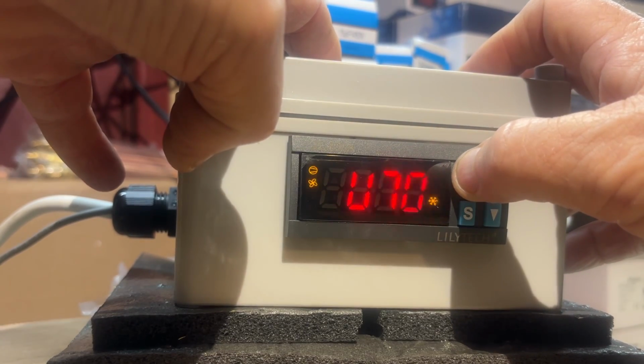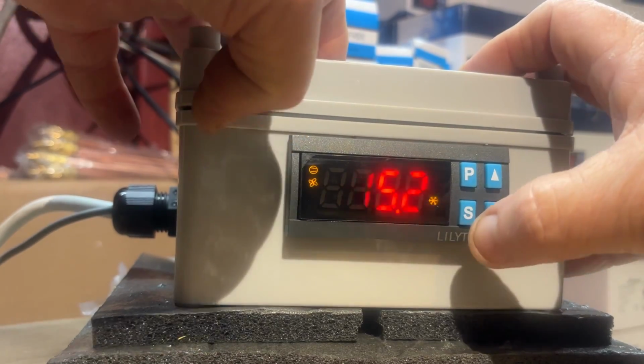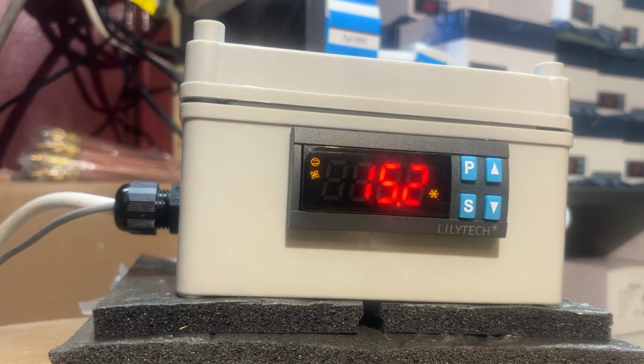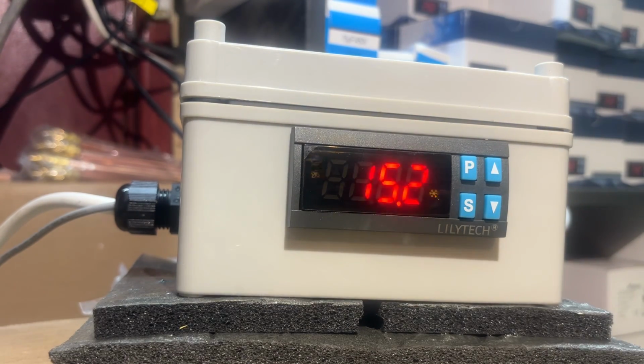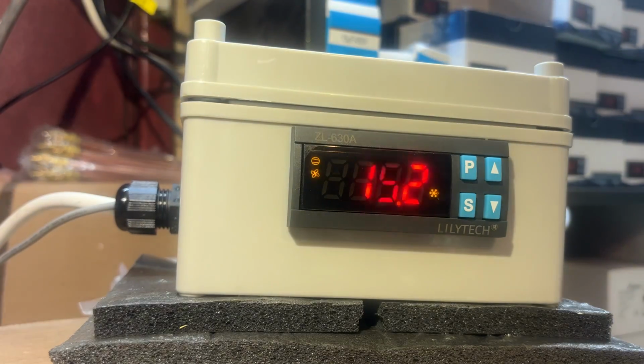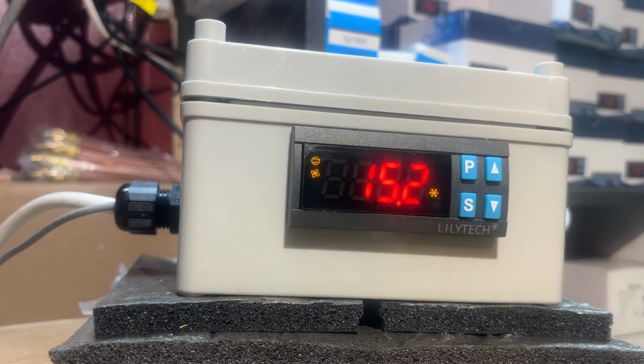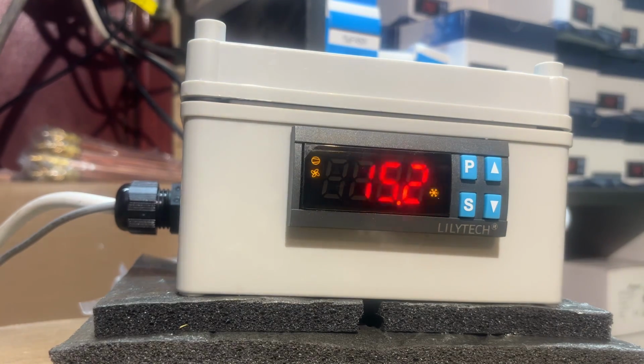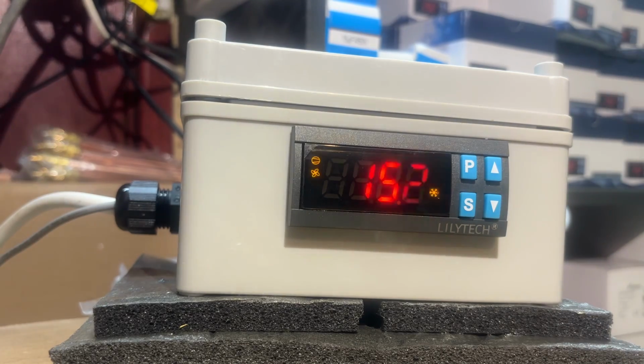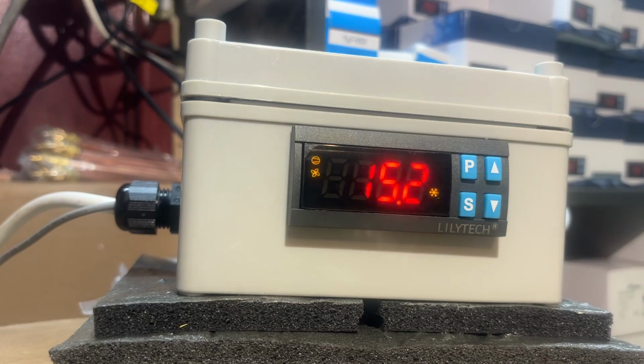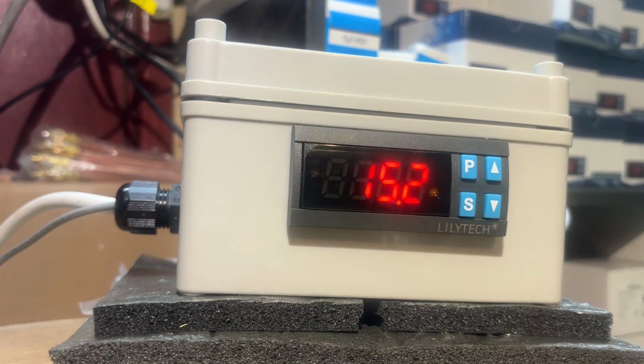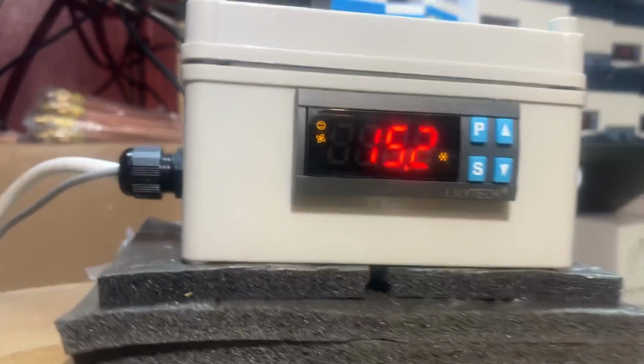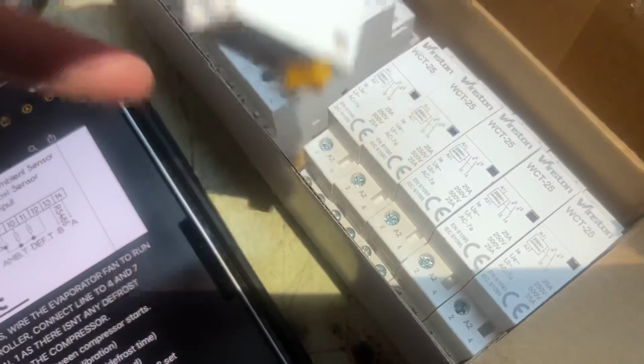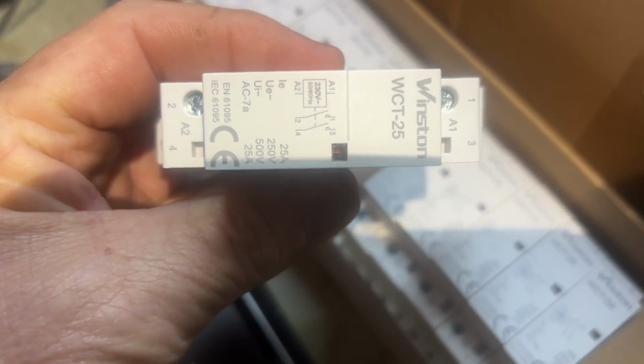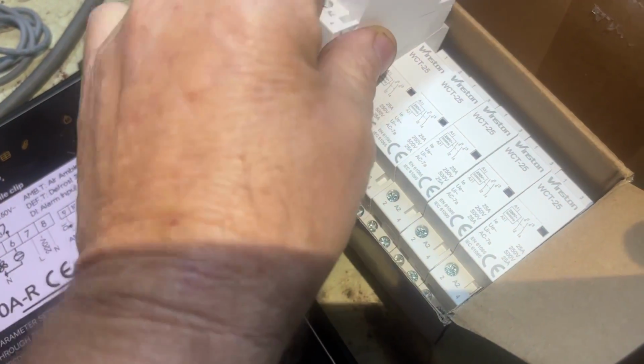Now, to lock all those parameters in, we have to push P and hold P in. Okay, so now they're all set, and this has a 10 amp relay in it for the compressor, and that's all we're using at the moment. You just wire the evaporator in to run all the time. Obviously there's no defrost heater, so you don't have to worry about defrost, and it's got a 10 amp, but I'd always put the compressor through something like this. This is just a 25 amp relay. I'd always switch it through a relay.